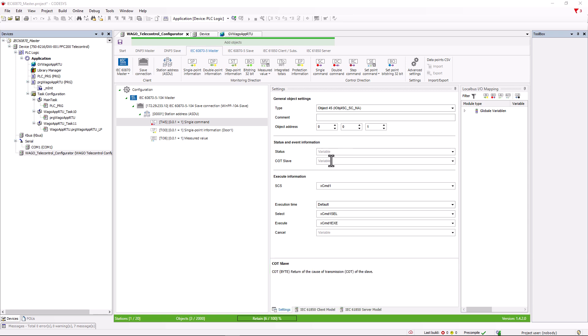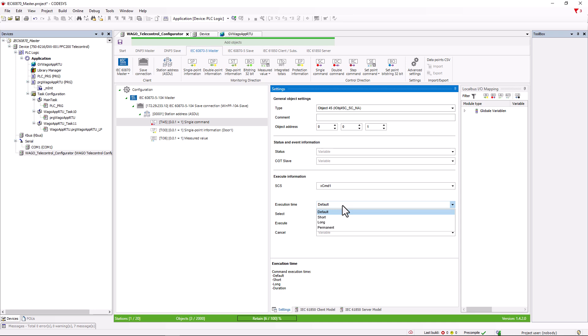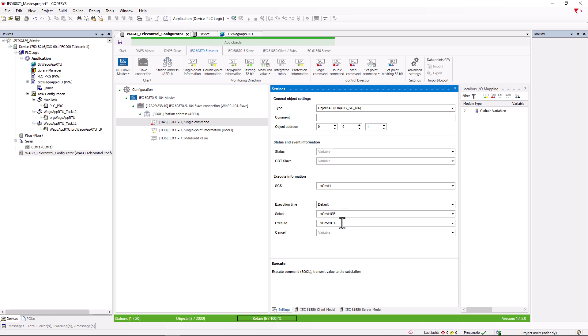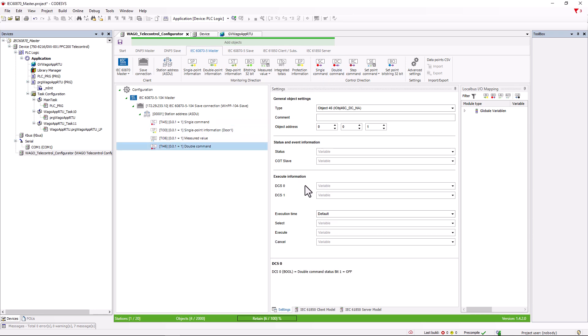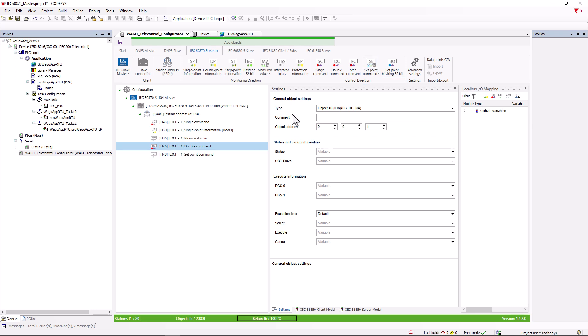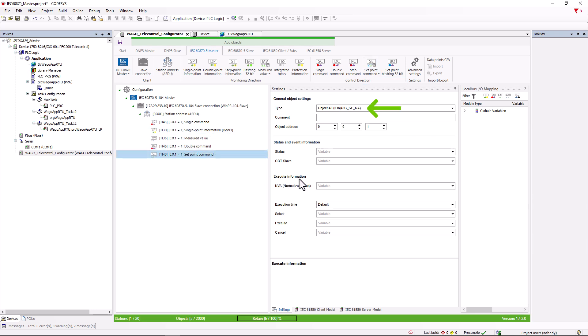Below this, we can create a byte variable to analyze the causes of the transmission. This is followed by the actual command variable and the execution time, whether the command is to be sent as a default, short, long or continuous command. And then, as already discussed, the variables for select, execute and cancel. The double command again contains two bool variables, usually one for on and one for off. And the setpoint command for setpoint transmission, which then sends a real or integer variable depending on the TI.